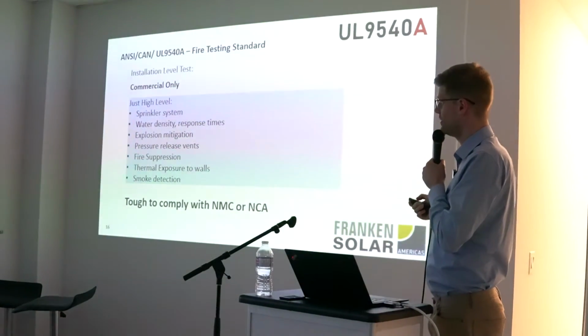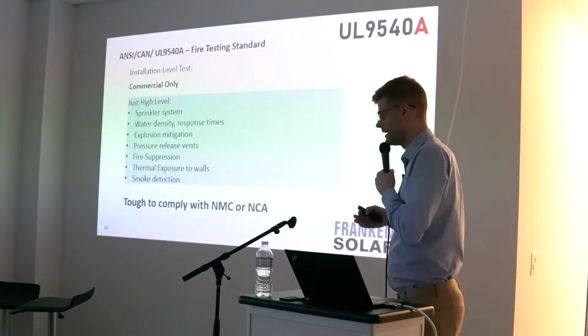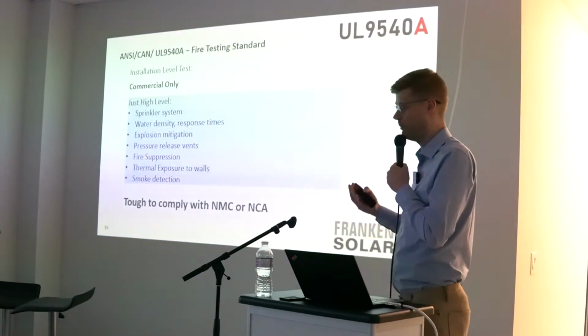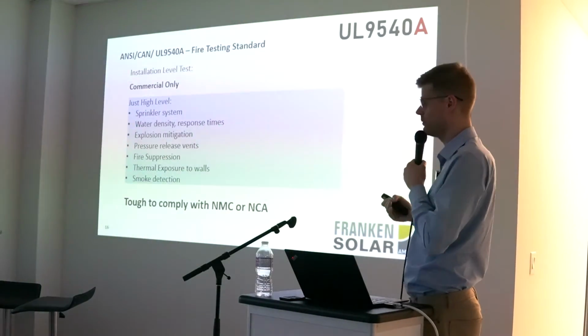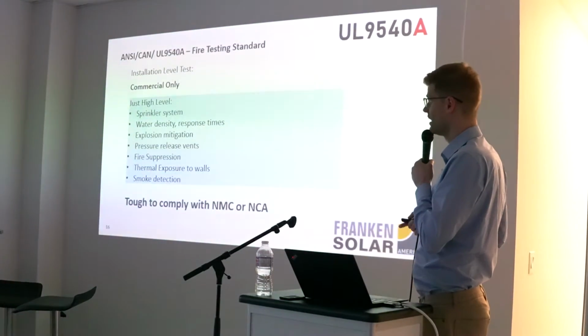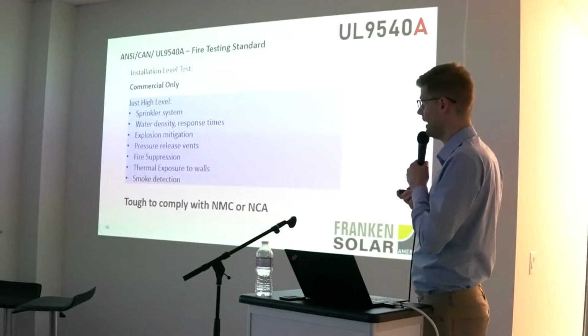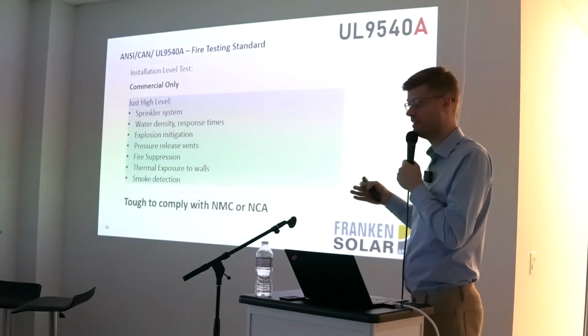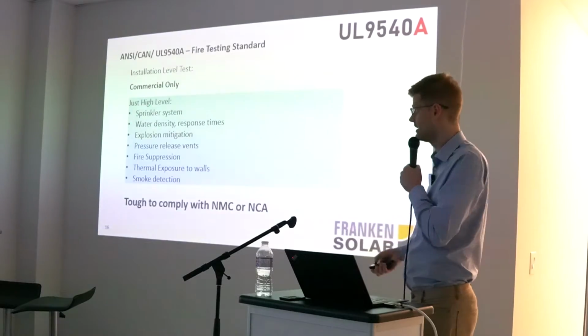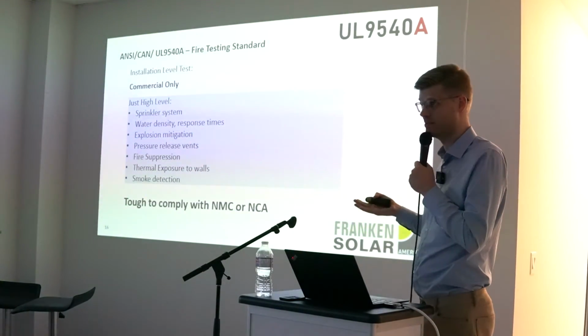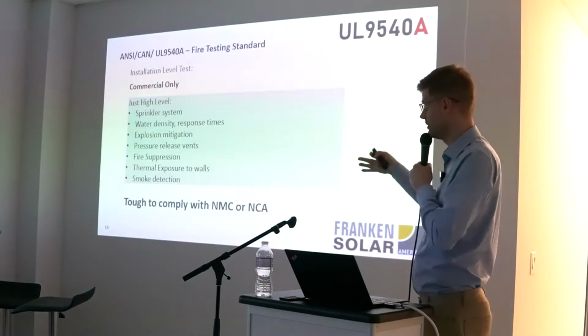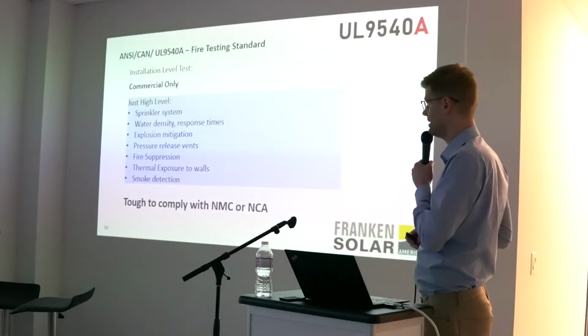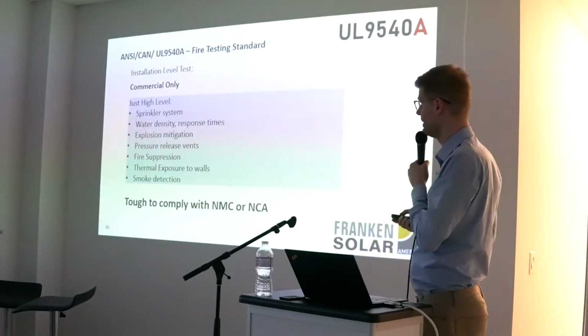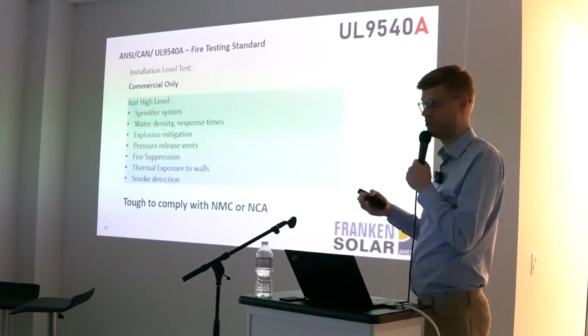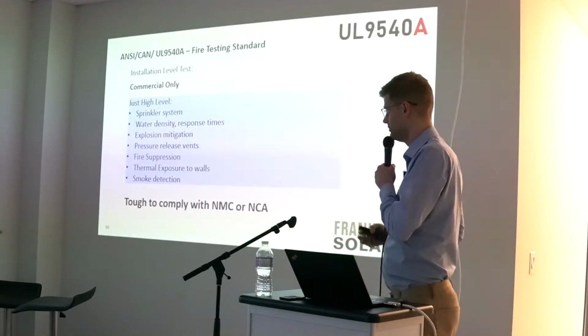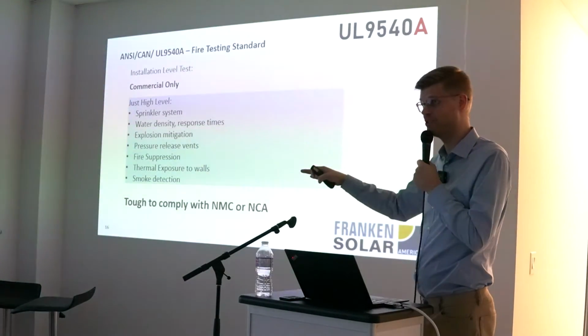And then the last test, and I put here right there, commercial only. Typically, if you have NMC cells from other manufacturers and not lithium iron phosphate, which is a little bit more benign to these systems, the manufacturer of that battery storage system has to add multiple levels of additional safety. They can choose whatever they need to pass that test. For example, that could be a sprinkler system in that container with a certain water flow and a certain sprinkler density to cool down that system and maintain that level. They can also use some fire suppression, where a CO2 or other fire suppression gas is inserted into that container.